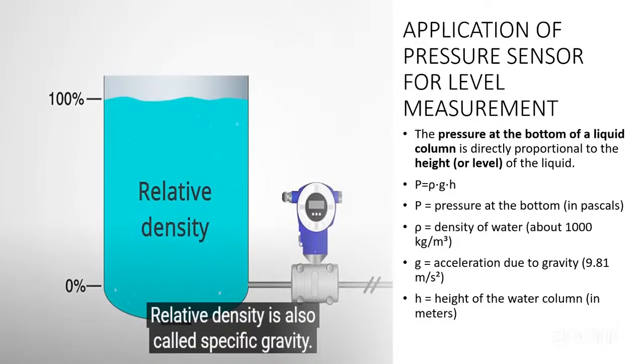So for those in the filling and packaging industry, you can take your mind back to machines like bottle washers and tunnel pasteurizers, or even buffer tanks. To achieve a desirable result, the pressure sensor must be mounted either at the bottom of the tank or by the side, very close to the bottom. For a vented tank, gauge pressure sensors are also used, like in the case of tunnel pasteurizers and bottle washers, which I mentioned earlier. Whereas absolute or differential pressure sensors are used for a closed pressurized tank.